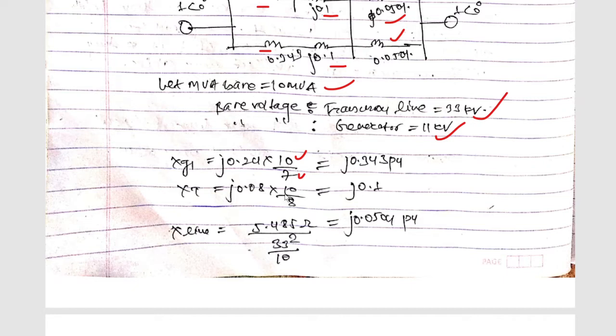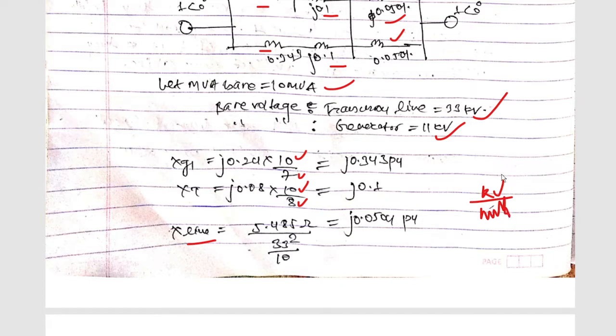Similarly for the transformer: 0.08 × (10/8) = 0.1 per unit. For the transmission line, it is actual impedance divided by base impedance. The actual impedance is 5.485 ohm. Base impedance for the line = kV² / MVA = (33)² / 10. So the line reactance = 5.485 / (33² / 10) = 0.0505 per unit.